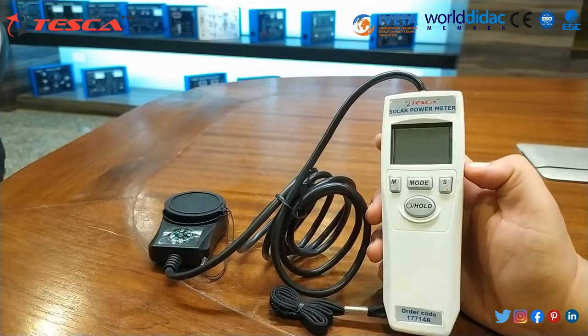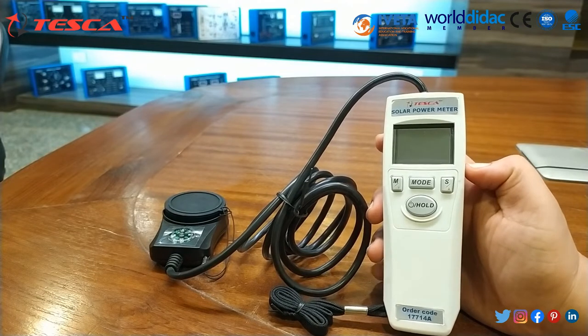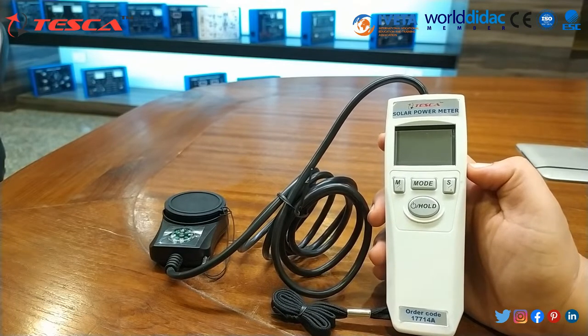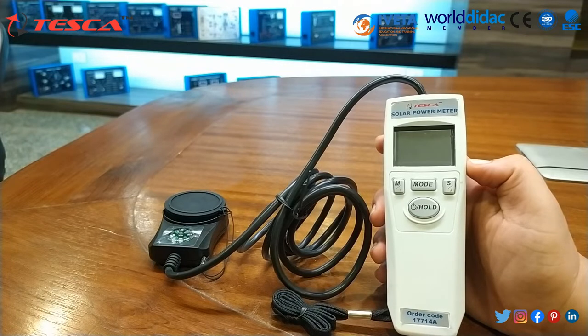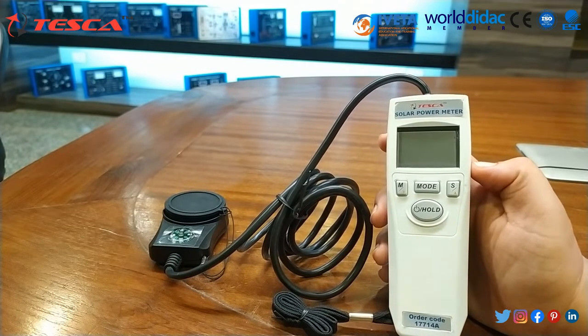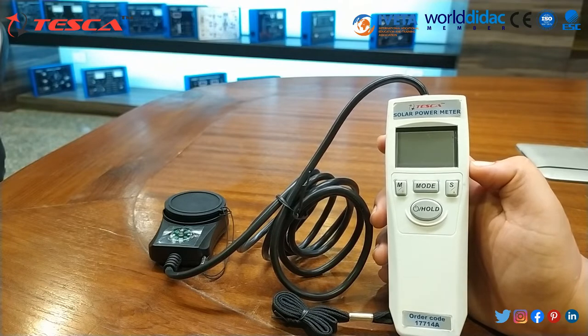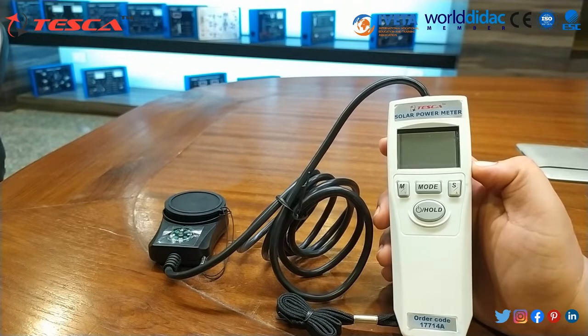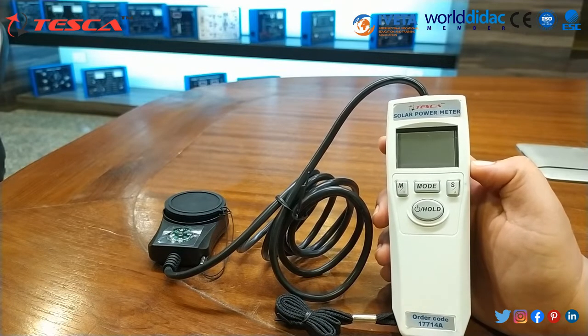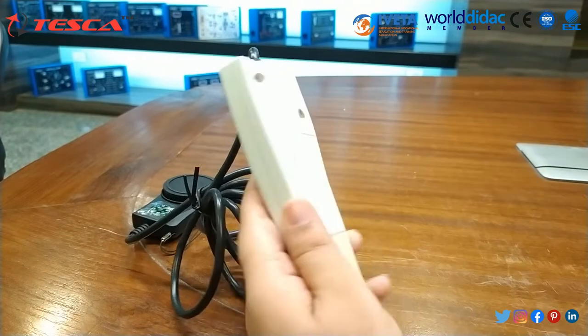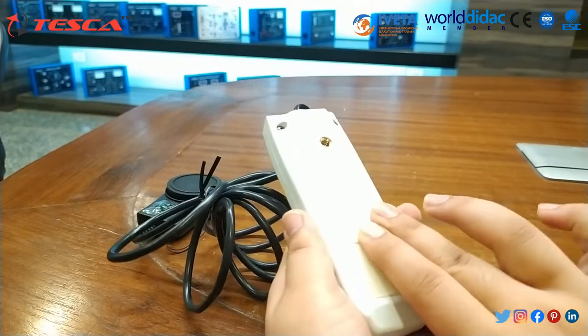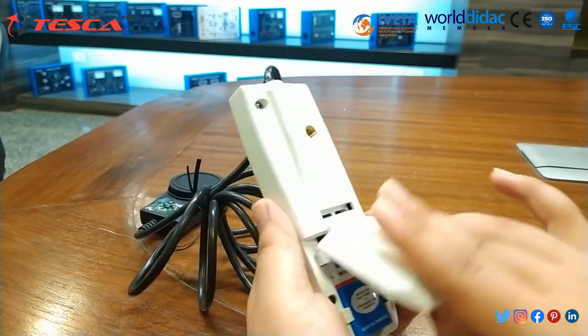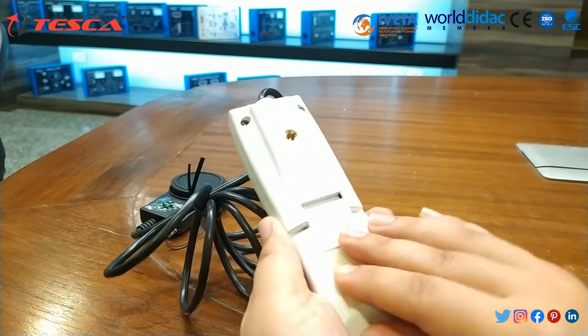The sensor used is a high sensitivity silicon photodiode which ranges from 0 to 2000 watt per meter square, and its resolution varies from 0.00 to 99.99 watt per meter square, and different ranges are also provided. Its tilt angle ranges from 0 to 90 degrees, and at the rear panel you have to connect the battery. In this way you can connect the battery.